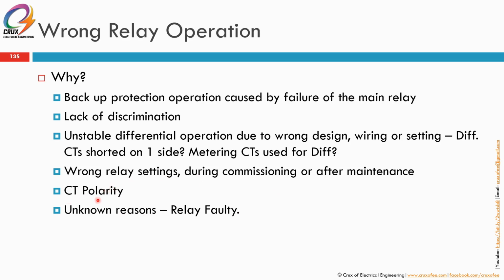Number 4 would be CT polarity. CT polarity is similar to wrong wiring. CT polarity will contribute to the CT reading wrongly. CT polarity is mainly important for those protections that require direction, for example differential and also directional protection, reverse power, all those kinds of protection. If it's just a normal overcurrent, then CT polarity is not an issue.